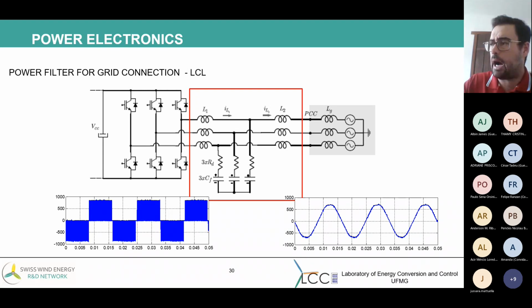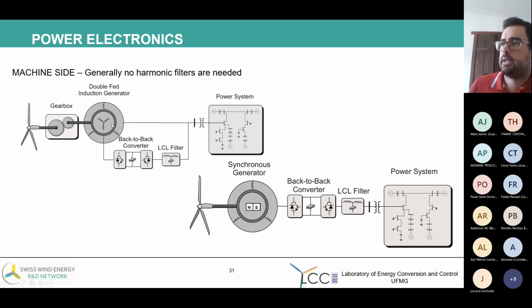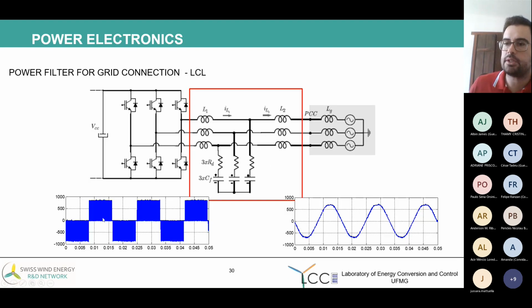And so we will always see, in the connection to the grid, the use of a power filter here in the DFIG. A filter here. For the PMSG, we see a filter here. It's always necessary to have a filter to connect the converter to the grid. The objective is to filter the voltage and have the desired behavior for grid connection.